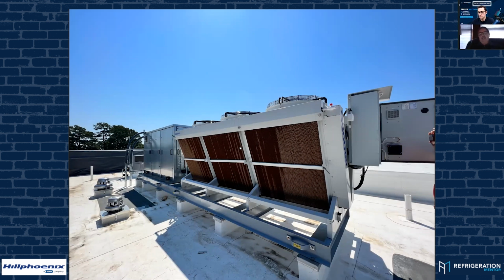So what's going to happen is this fan's going to go into a 4-minute, what they call wetting period. And this rack is just going to run wide open with water. You'll see a stream of water coming out the drain, probably an inch or better thick. And what that's doing is it's saturating the cellulose to get it nice and wet. And then after that pre-wet program ends, you're going to go into the control mode. Using the probe that's in between the pads and before the condenser, and whatever the algorithm's calling for, it's going to wet and dry. You can see it's just wetting it a little and drying up. You'll watch it dry up, and then you'll watch it wet again. And at that time, it's just piddling out a little bit of water while it's operating.